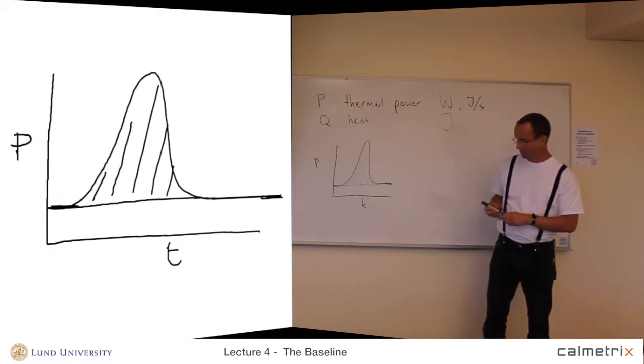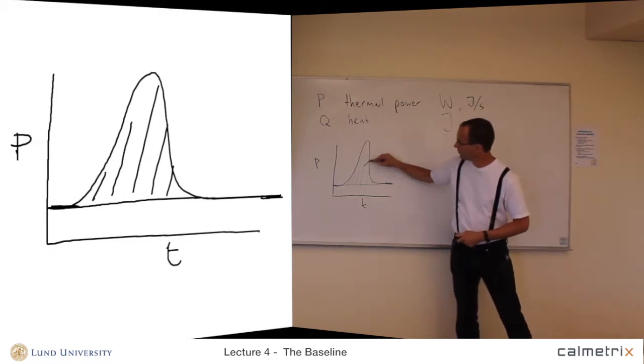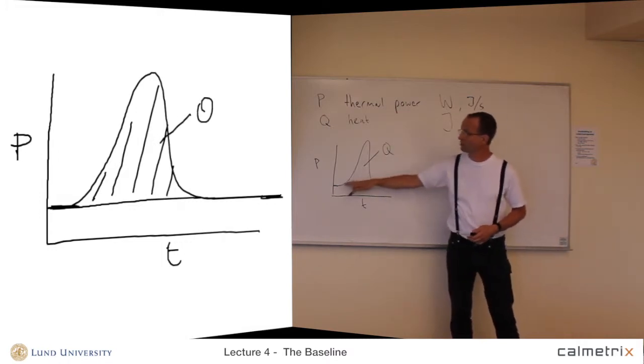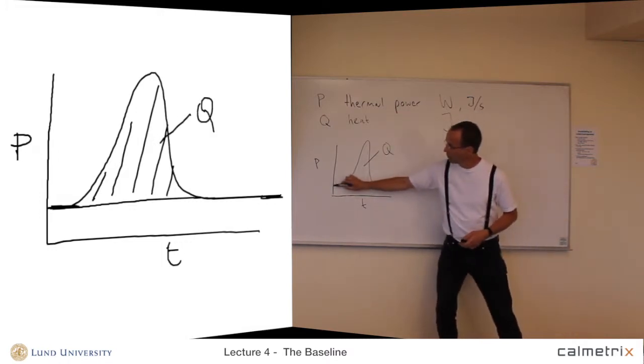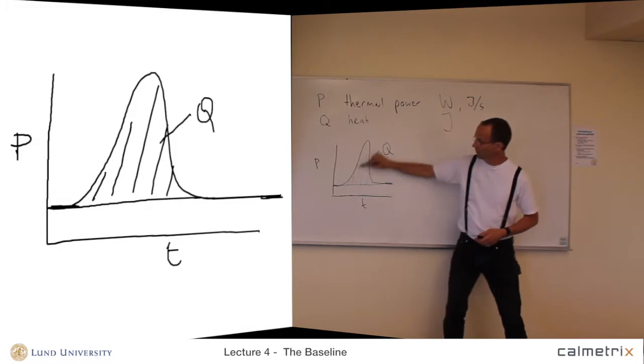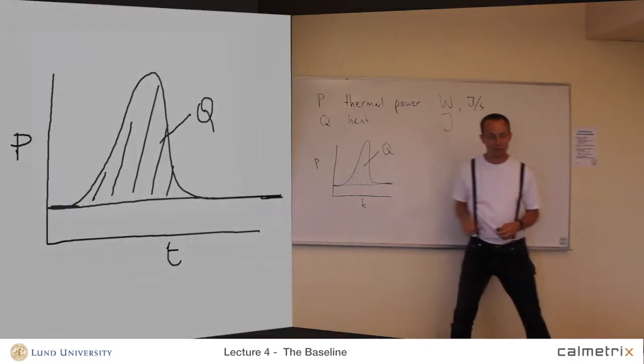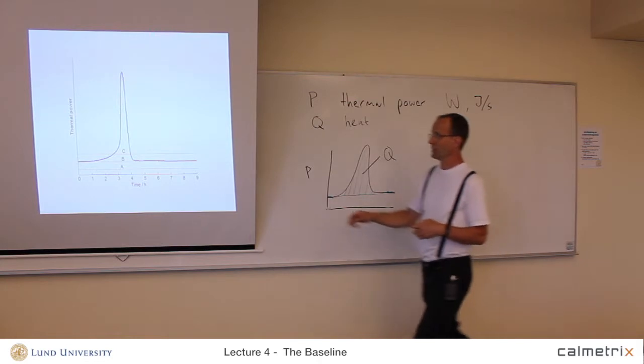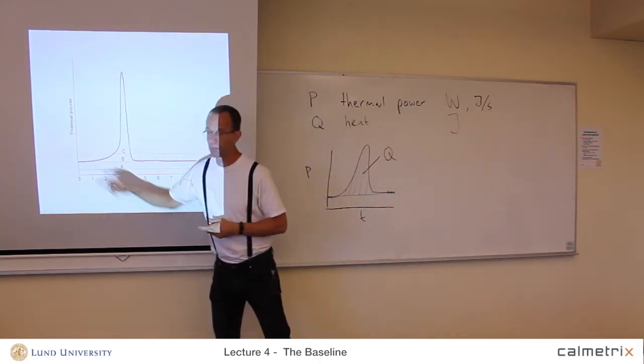If we want to evaluate how much heat this reaction produced, we need to know the baseline, and then integrate the peak over the baseline to get Q. So in this case it's very important to know the baseline, but it's easy to take the baseline directly from the measurement.